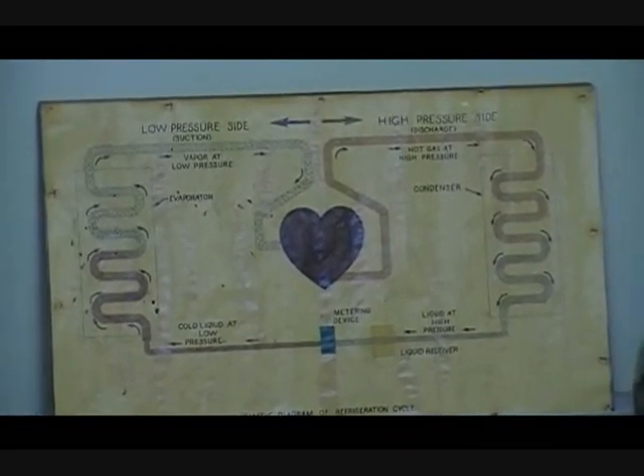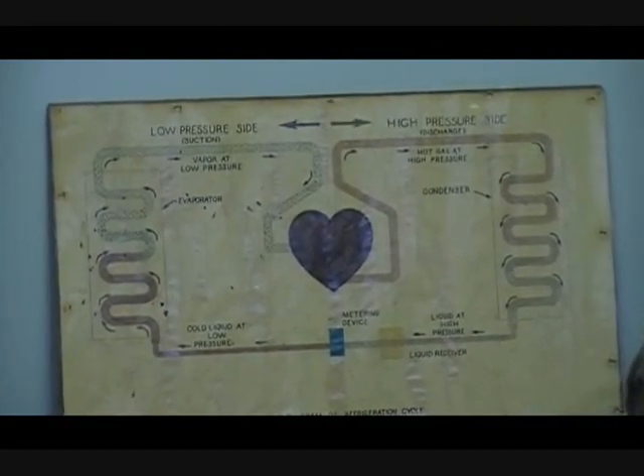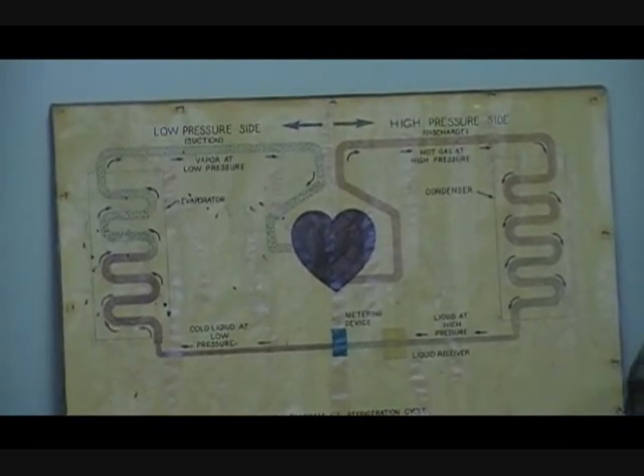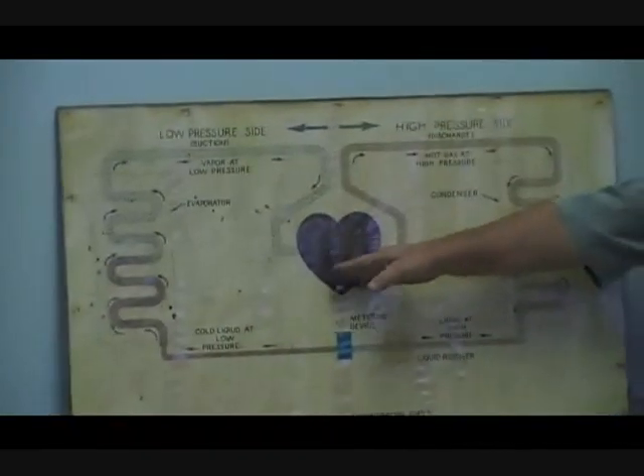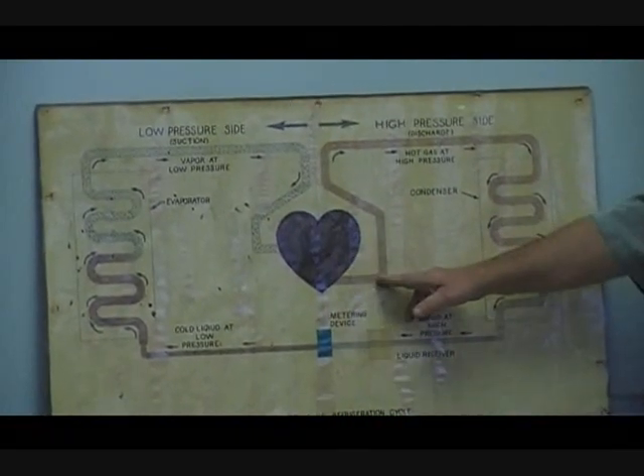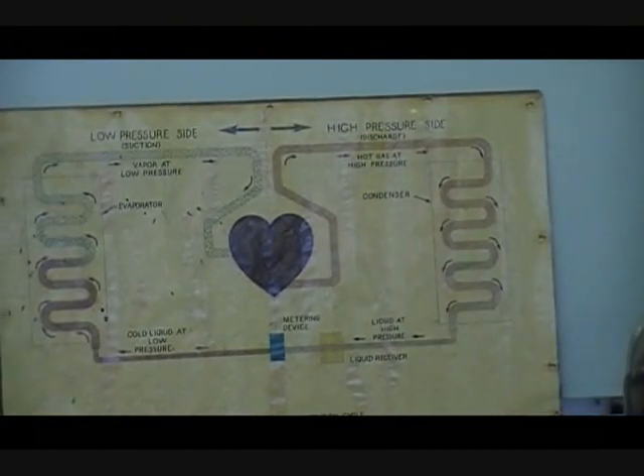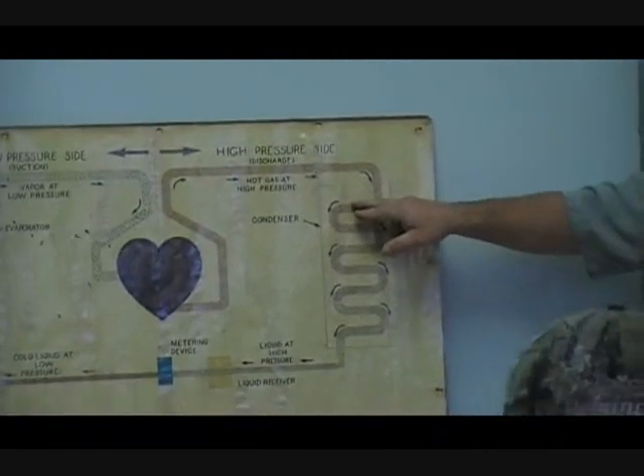Now let's get a little more detail. I'm going to use not exact pressures or temperatures and describe what's happening, and then we'll go back and do one using some typical pressures and temperatures. Let's look at the compressor. The compressor takes a low-pressure gas, compresses it to a high-pressure gas, and it enters into the discharge line as a superheated high-pressure gas. Remember that term superheated — it's above the boiling point. It goes into the discharge line and enters into the condenser.